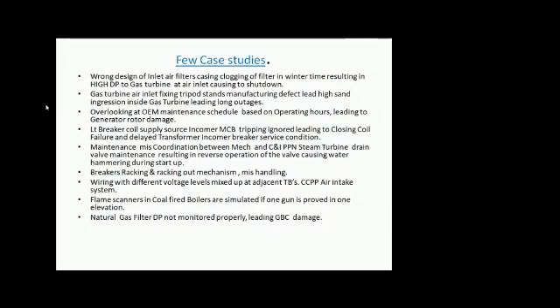And the other thing is maintenance miscoordination between the mechanical, the C&I and the electrical teams. One classical example which I have seen in my own experience is that a steam turbine drain valve had to be taken for maintenance. Some gasket had to be replaced, so the maintenance had to be done. The C&I part is to remove the actuator. Once the actuator is removed, the mechanical people take up the maintenance, and they replace the spares or whatever it is inside. Again, C&I puts the valve back and the machine was started.